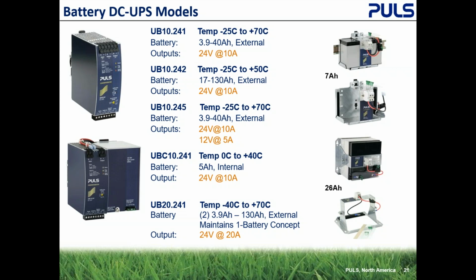You also see we sell some batteries on the right. We're not a battery manufacturer, we go up to 26 amp hour. I know some of the gas and oil people want 100 or 150 amp hour batteries, we don't supply those, again we're not a battery manufacturer. We have these available for convenience for our customers. But we can take, say for instance the 20 amp unit on the bottom, we can take up to 150 amp hour batteries now, and give you a couple of days at an amp and a half.